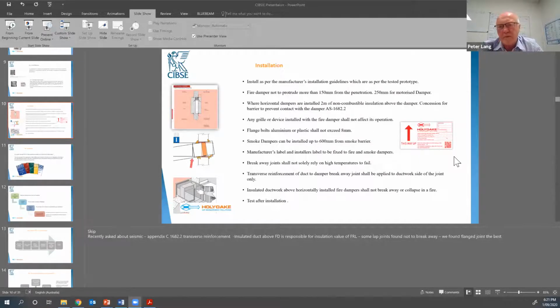So what about smoke dampers and smoke spill dampers? Are they usually on the air side as well? Yeah, smoke dampers they are. We always put them on the inside, so that they're easy to see. And we generally try and put them halfway up the wall, the left-hand side of the damper, if you were looking at it face on. So they're relatively easy to spot. But if there's no access panel for a smoke damper, how do they see it? You'd have to see it with a camera, but again, there should be a log on site. You should be able to see it with the building data, and there should also be a label on either the wall or the duct adjacent to the damper.